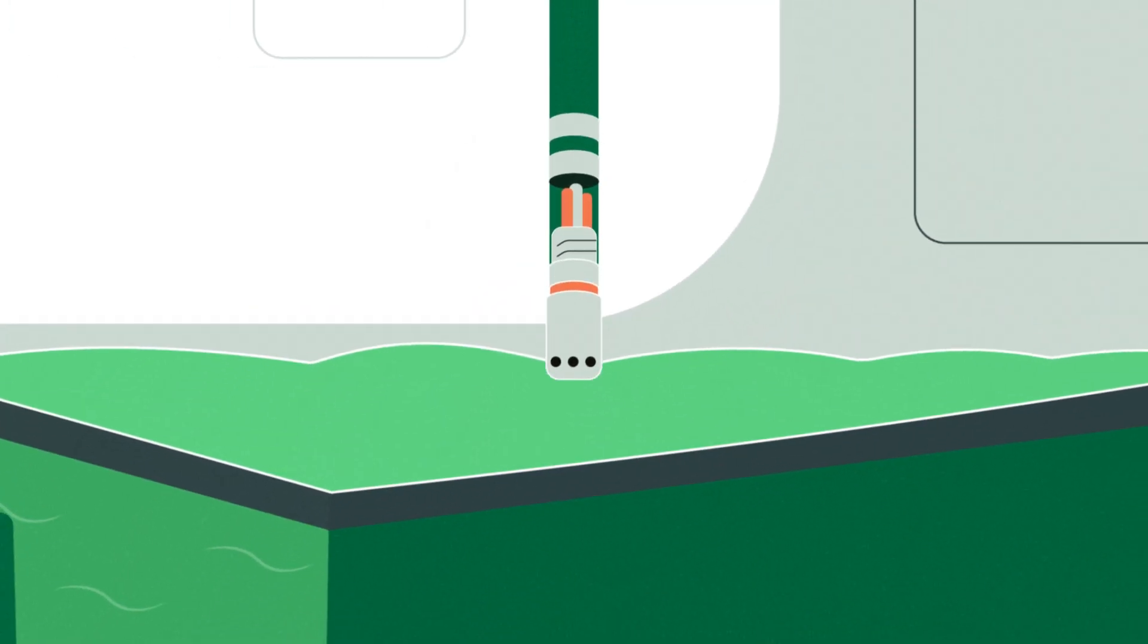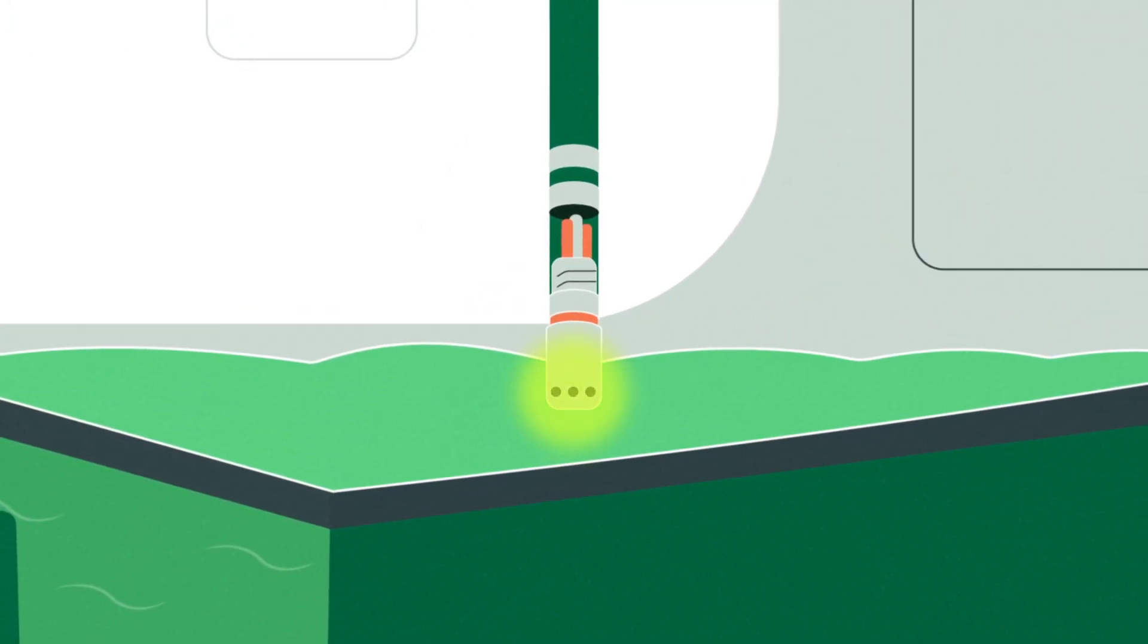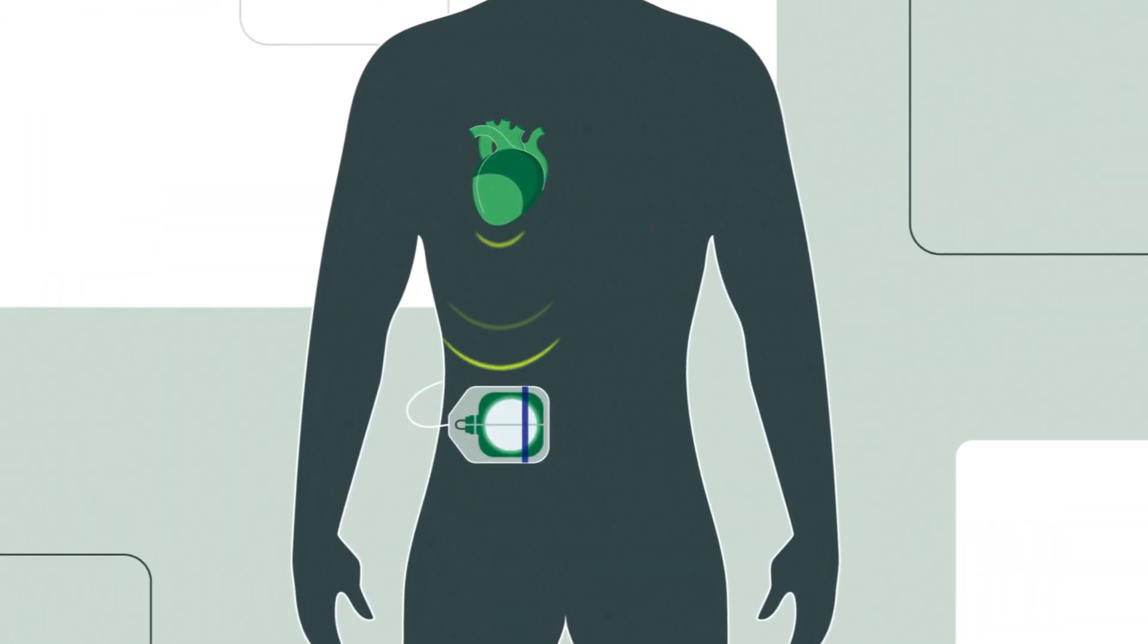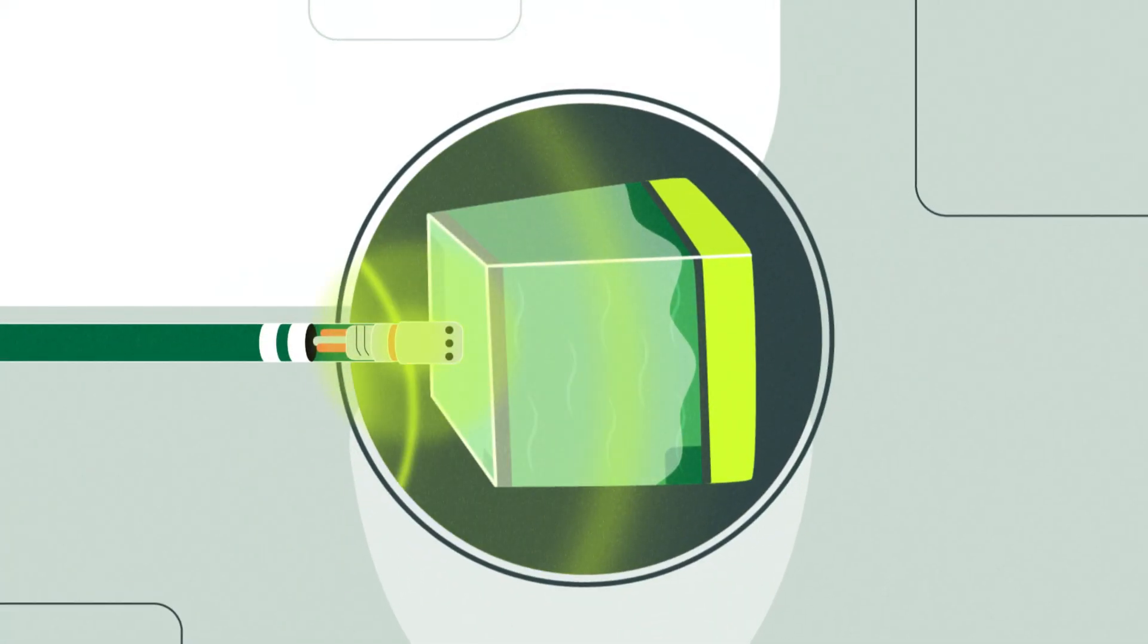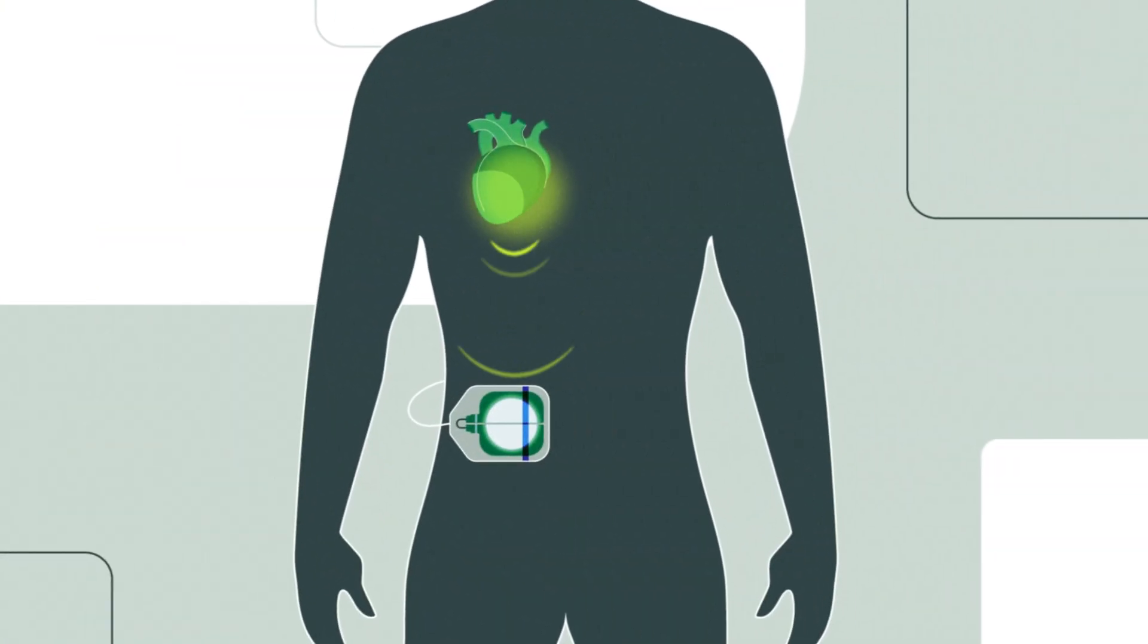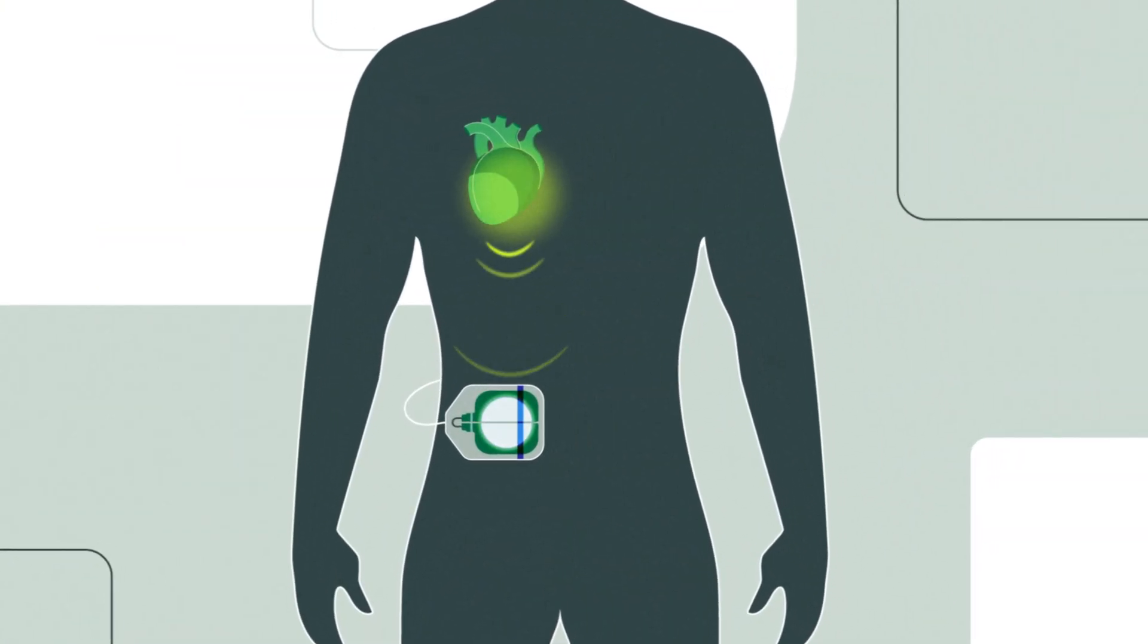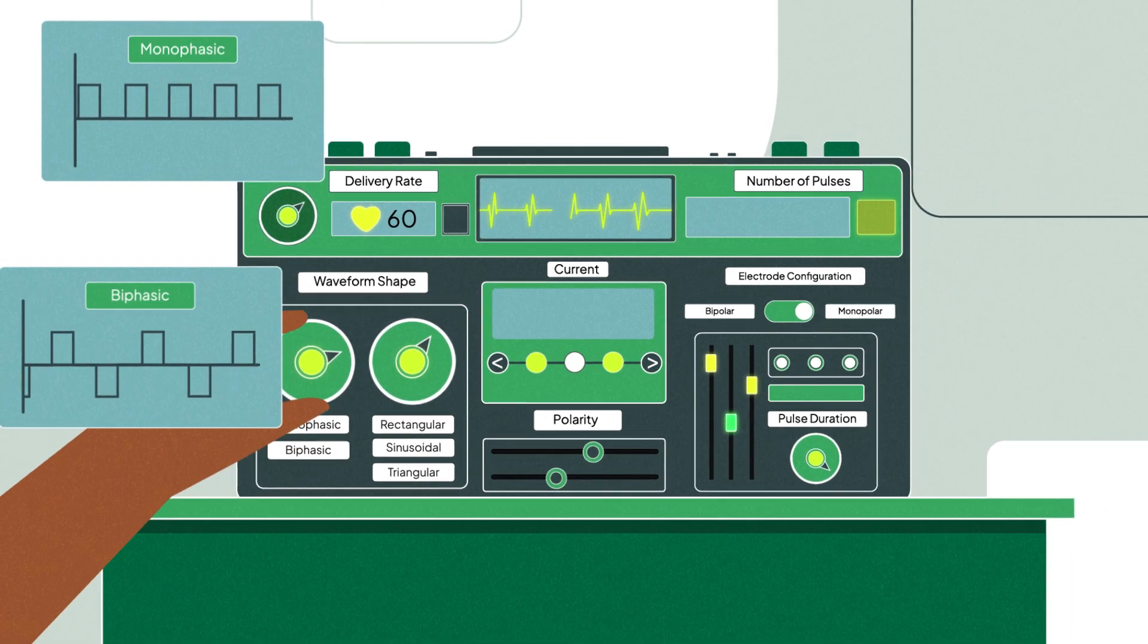In a monopolar configuration, an electric field is created at the catheter tip and directed towards a remote dispersive electrode, achieving deeper lesions. While the larger span of monopolar fields can increase the potential for muscle stimulation, waveform design can be tuned to mitigate this.